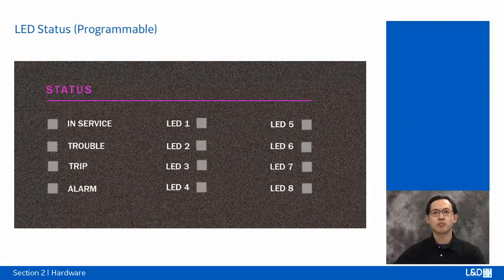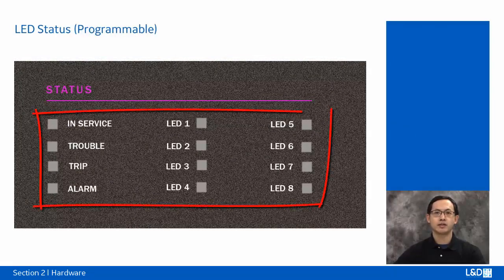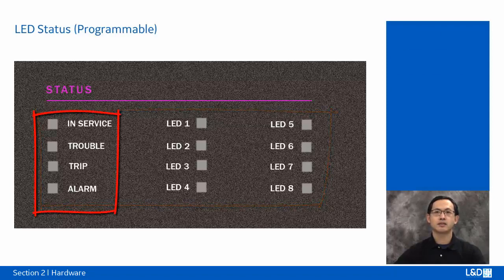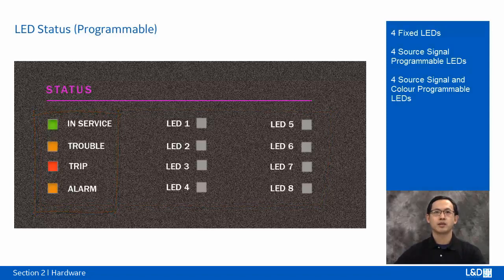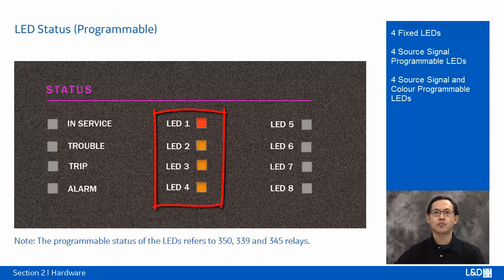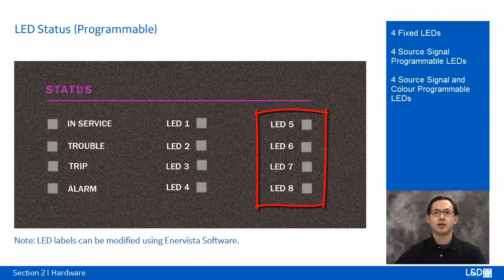Front panel with programmable LEDs has 12 LEDs. The first column LEDs are dedicated to in-service, trouble, trip, and alarm, with the same color convention as the non-programmable LEDs. The second column is for the source signal programmable LEDs 1 to 4. LED 1 is red; 2, 3, and 4 are orange. The third column is for LED 5 to 8. They are programmable in source signal and also in 3 colors: red, orange, and green.